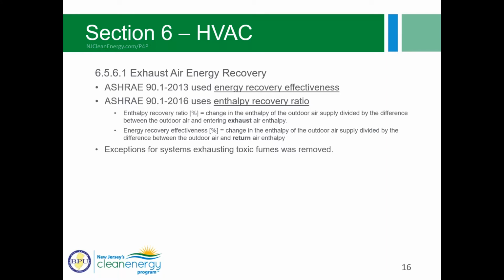All right, for exhaust air energy recovery, this is a terminology change between the two codes, where in 2013 there was energy recovery effectiveness, and 2016 has enthalpy recovery ratio. So they changed the metric just slightly. And this, again, points back to the terms that are italicized, that it's always good to make sure that we're looking at those and applying the right metrics when we are looking at compliance or building the energy modeling. Also, they changed this so that the exceptions for systems exhausting toxic fumes was removed.